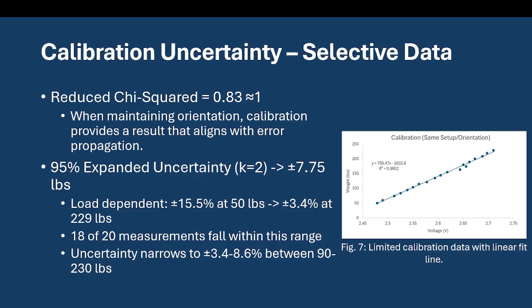When we isolated just the first of the 3 data sets, same orientation, same setup, the picture improves significantly. The reduced chi-squared drops to 0.83, which is essentially 1, meaning the calibration residuals are fully consistent with what error propagation predicted. The expanded uncertainty is plus or minus 7.75 pounds, half of the full trial result. More importantly, at the loads this scale is actually designed for, 90 pounds to our max tested value of 230 pounds, that works out to between 3.4 and 8.6%, which is closer to our theoretical 3.93%.